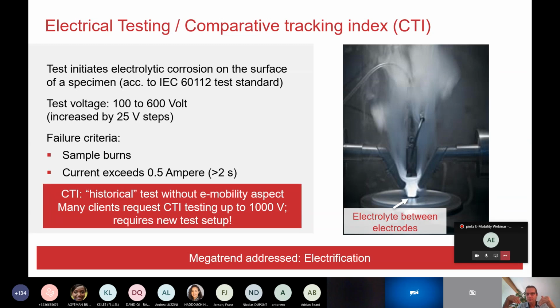Basically, these tests operate with two electrodes. You apply a voltage and you create a current flow in between the electrodes on the surface of the material. And at that point, the characteristics of the material come into play: the water take-up of the sample, the conductivity, electrostatics, and things like that. As I said, a historical test designed up to 600 volts. In the meantime, our clients consider 800 volts, 1000 volts, and so on.